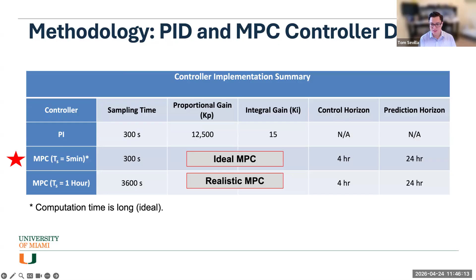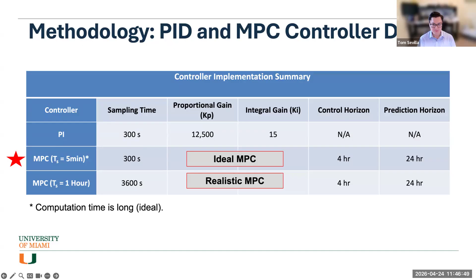And the reason that this happens is because the way that we're controlling our current model, we're just directly commanding the cooling load, and that's essentially in watts. So in a practical HVAC system, your PI gains are typically much smaller in magnitude since the controller usually modulates kind of an intermediate actuator, so things like a valve position or a damper angle or the VFD speed. You're not directly controlling the thermal power. In this case, we are controlling the thermal power directly, which is what gives us those very large gains.